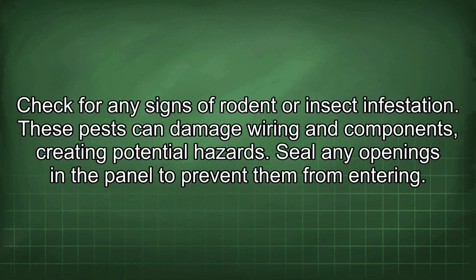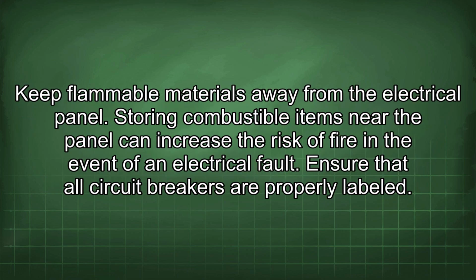Check for any signs of rodent or insect infestation. These pests can damage wiring and components, creating potential hazards. Seal any openings in the panel to prevent them from entering. Keep flammable materials away from the electrical panel. Storing combustible items near the panel can increase the risk of fire in the event of an electrical fault.